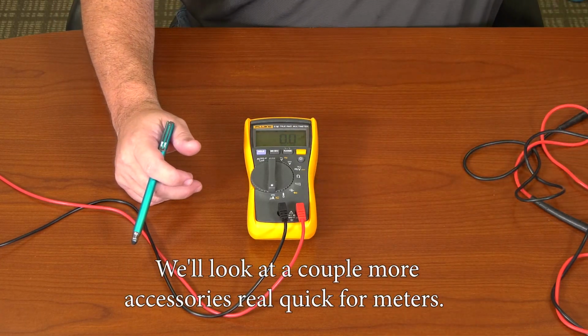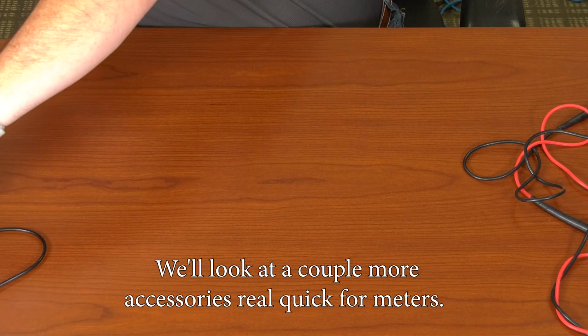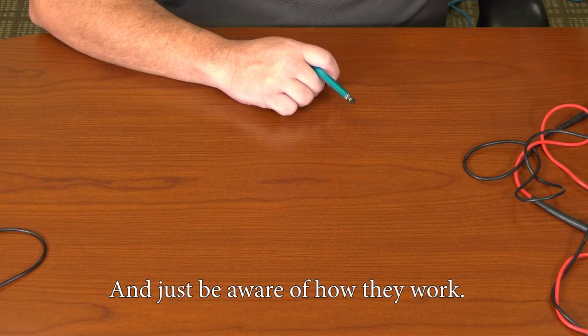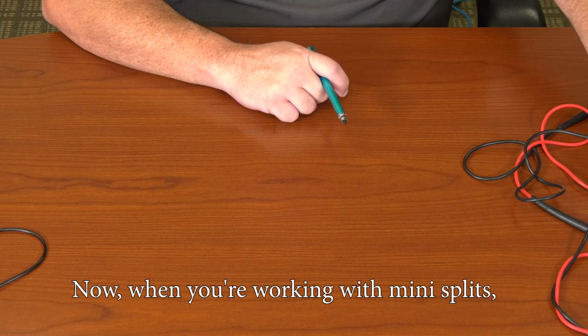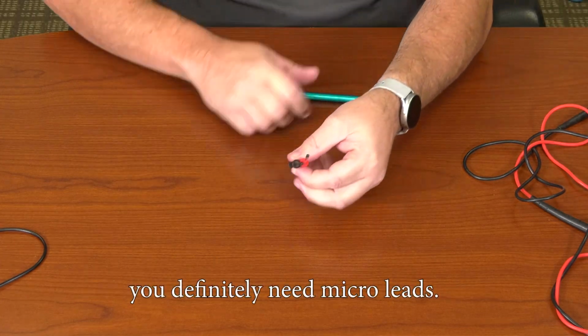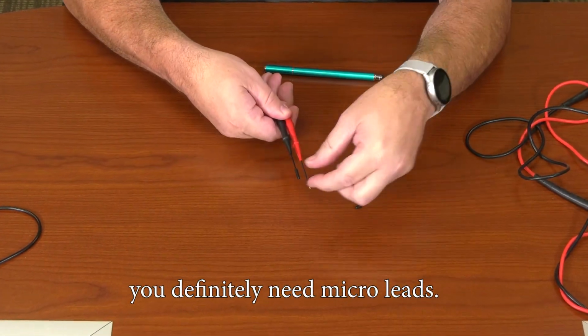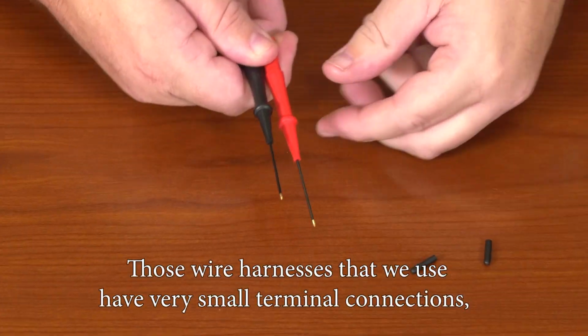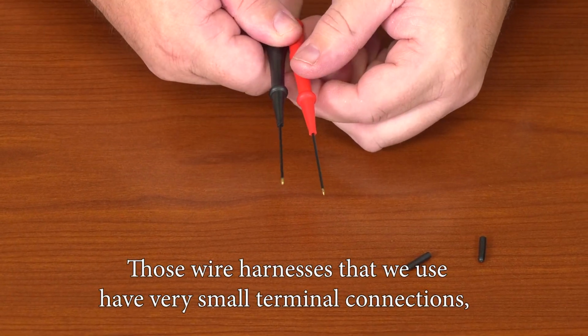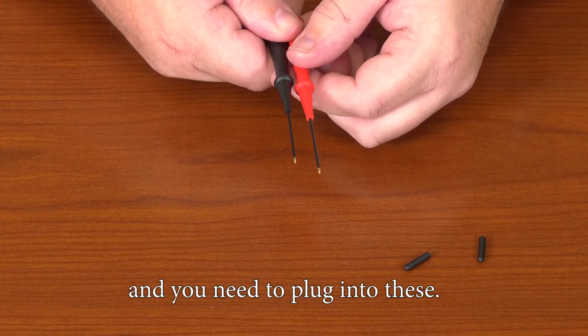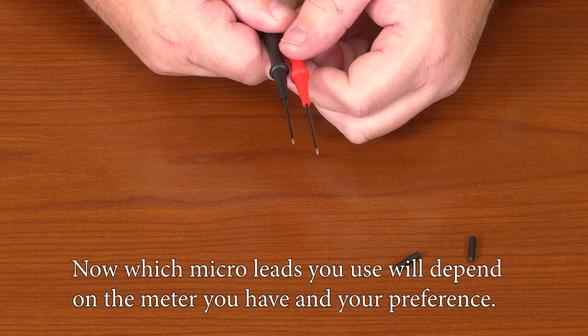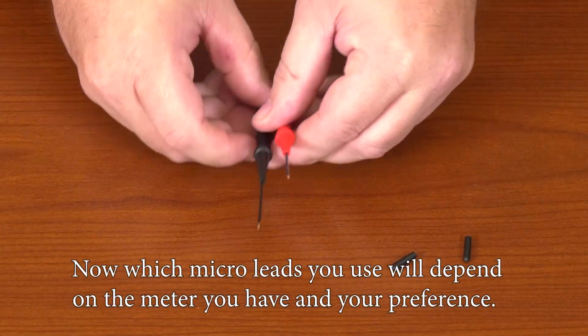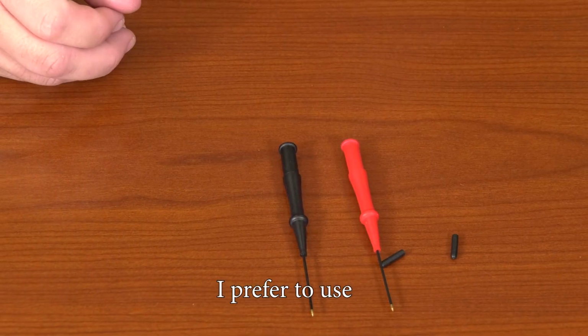We'll look at a couple more accessories real quick for meters and just be aware of how they work. Now, when you're working with mini splits, you definitely need micro leads. Those wire harnesses that we use have very small terminal connections, and you need to plug into these. Now, which micro leads you use will depend on the meter you have and your preference.